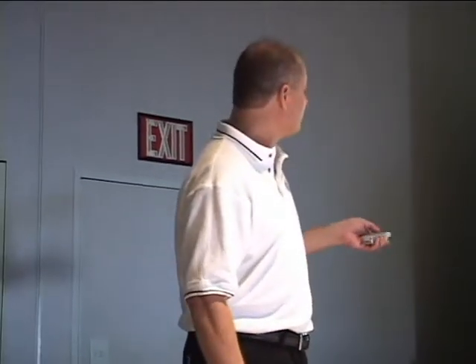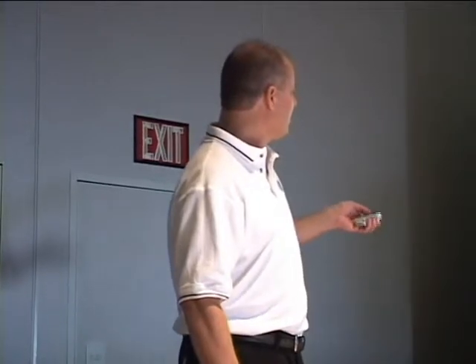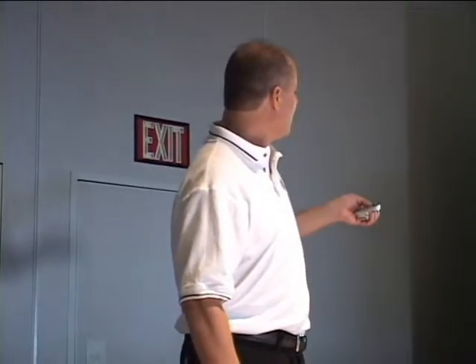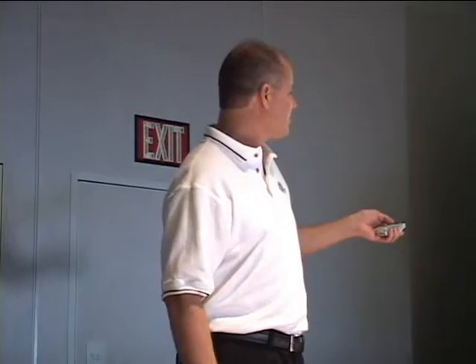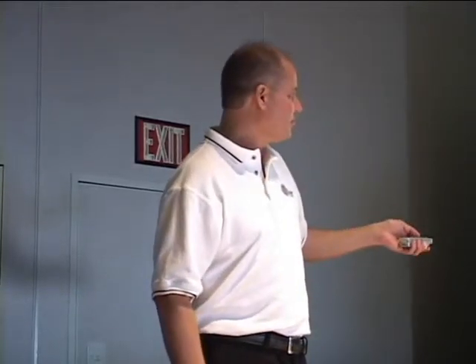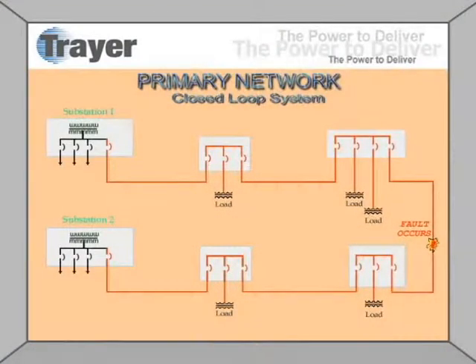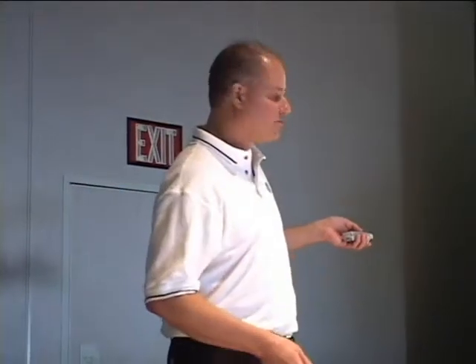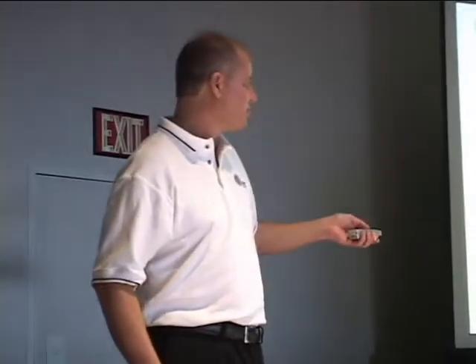If this were an open loop system or a radial, remember we had an open point here, all of that 10,000 amps has to go through our elbows and cable and equipment to get to the fault. In a closed loop system, we share that current from both sides. And this isn't exacting, but my point is you've got maybe half, or close to maybe only 5,000 amps going through the equipment instead of 10,000 amps like you would with an open loop or radial.